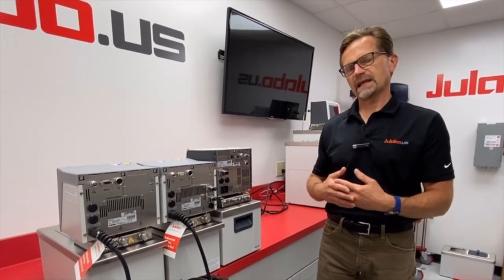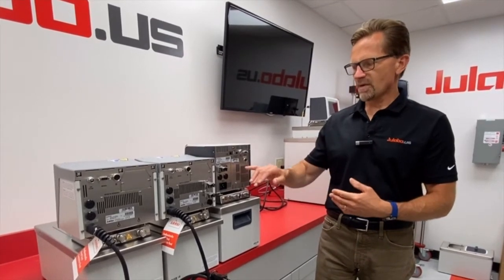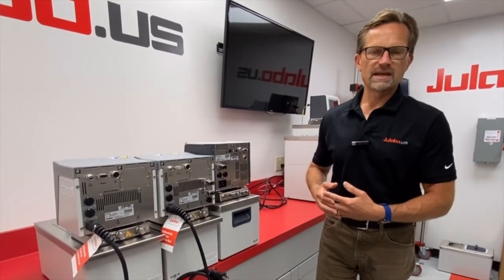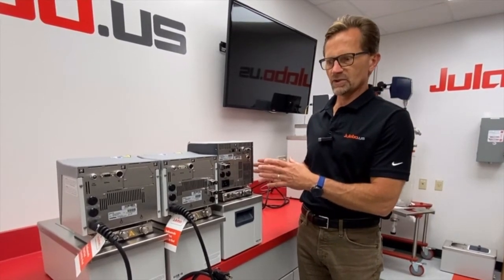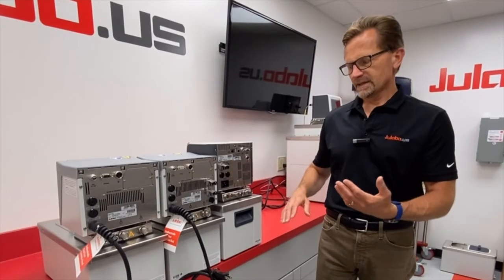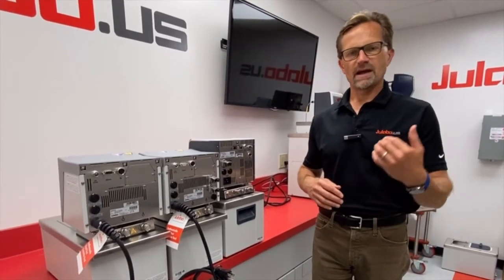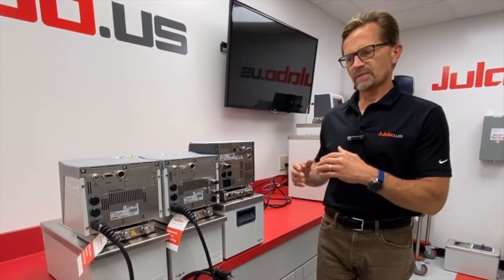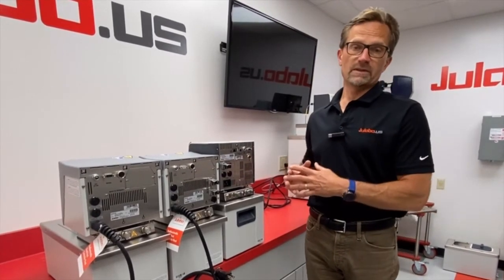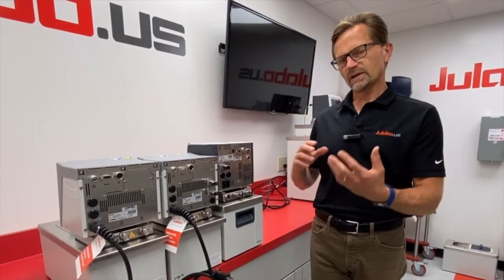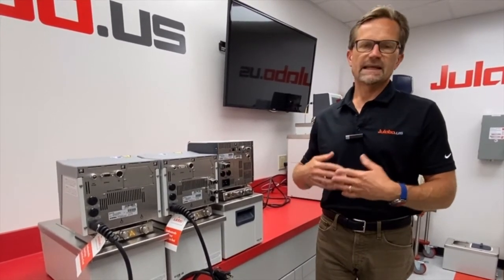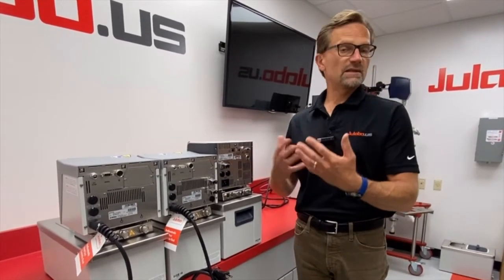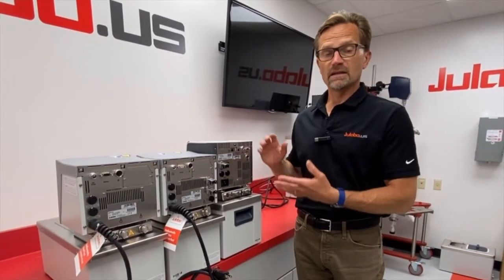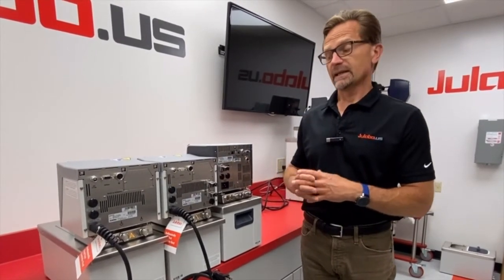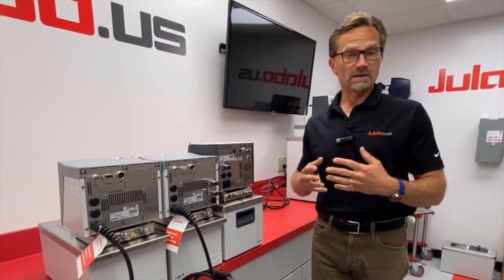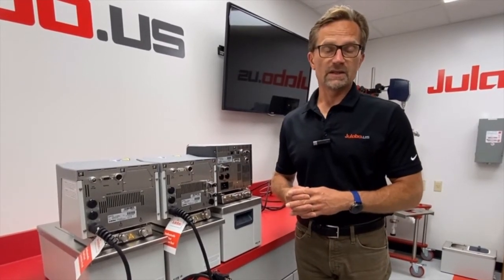But if you have a more sophisticated communication setup that requires Ethernet or USB, then in that case the MAGIO is the obvious choice. Also from a pump perspective, since the MAGIO has a stronger pump for a higher flow rate and higher pressure, if your application requires that, then the MAGIO is the way to go. And certainly from a user interface, usability, ease of use, and to see quickly at a glance what is going on, the MAGIO's large color TFT touchscreen is up to date with modern technology compared to the older screens on the HE and the HL.